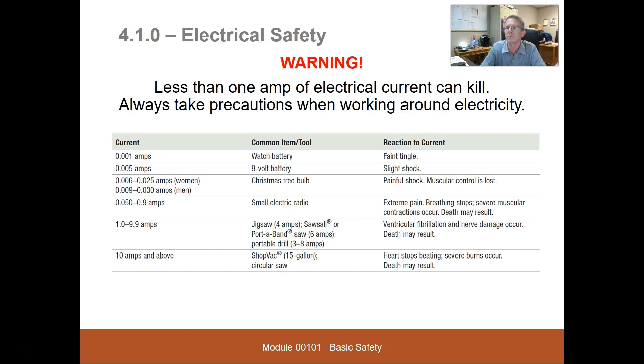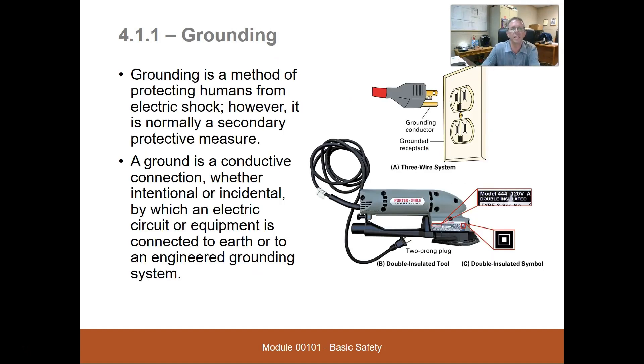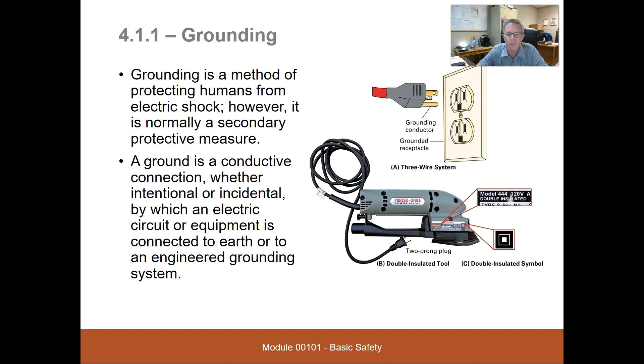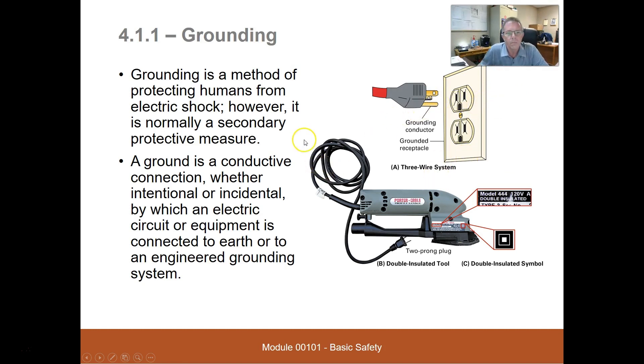Grounding is described as a method of protecting humans from electrical shock, but it is normally a secondary protective measure. A ground is the conductive connection — intentional or accidental — by which an electric circuit or equipment is connected to the earth or to an engineered grounding system. A three-wire cord has one wire for hot, one for the grounded conductor, and one for the grounding conductor, which connects back to the panel, down a grounding electrode conductor, to a grounding electrode, and into the earth.